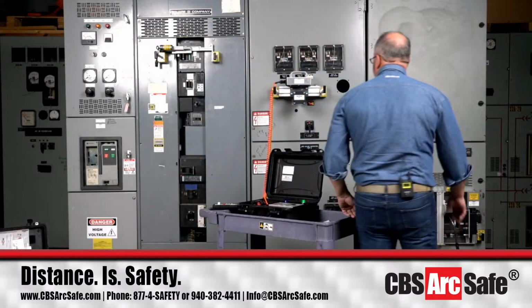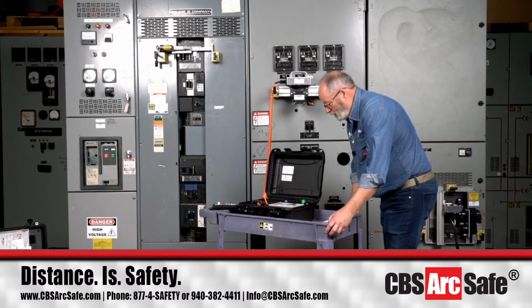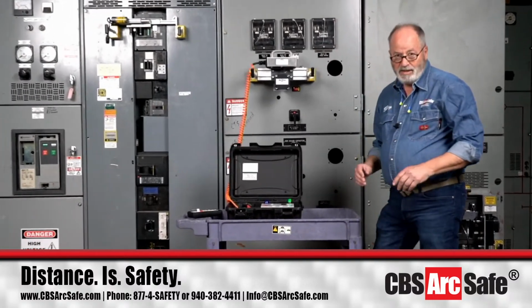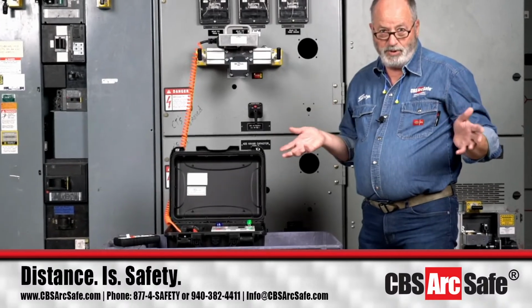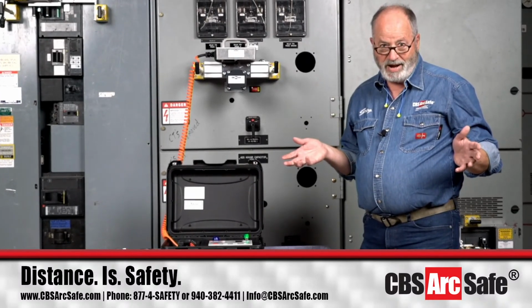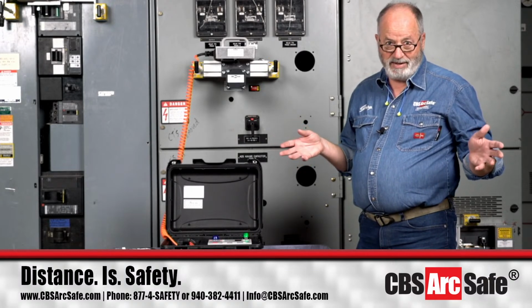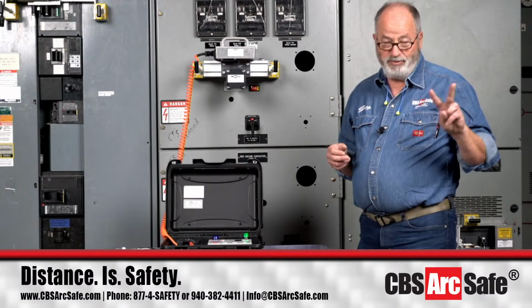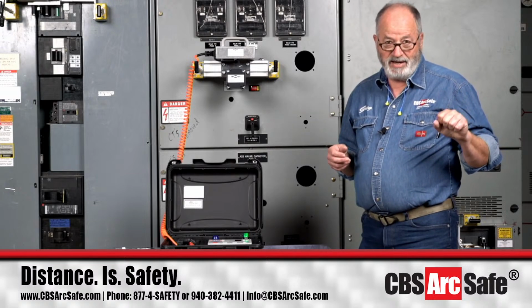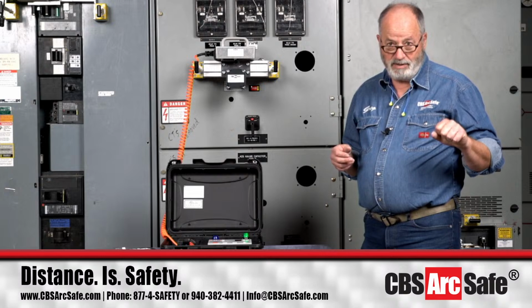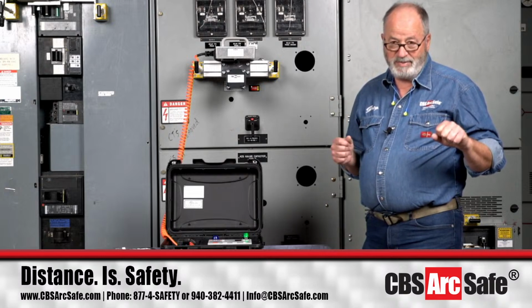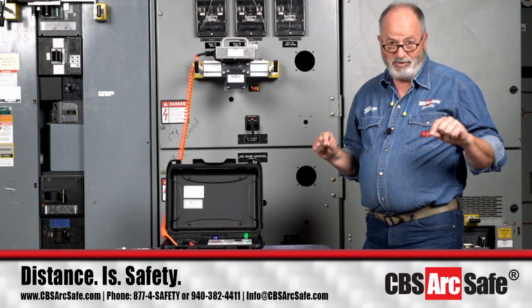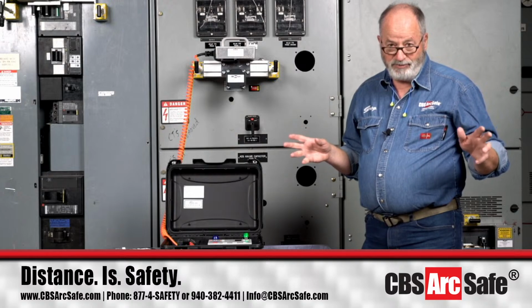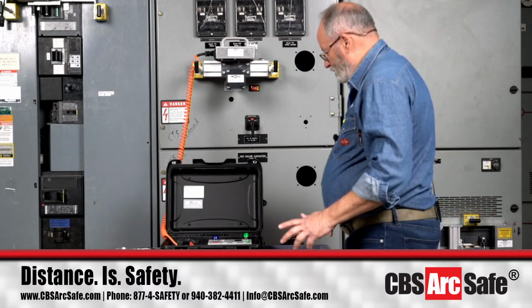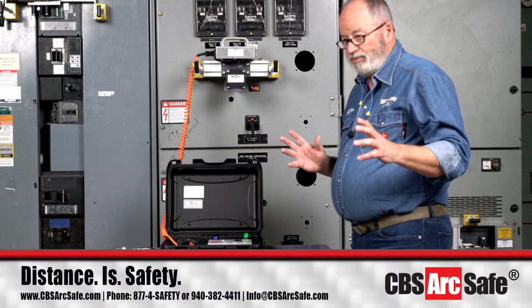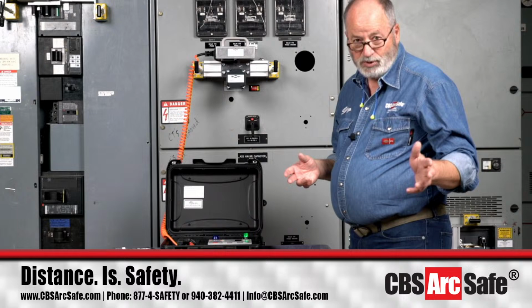So this has install 4.5, remove 3.0. One thing to understand is breaker manufacturers won't put the torque numbers required for racking a breaker in and out into their manuals unless you, the customer, demand it. Honestly, we've only seen 2 manufacturers put recommended torque inside their manuals in the last several years - 2012 was the first time I saw it, and it's still not in every manufacturer's manual. So this is something you'd have to ask the switchgear manufacturer about.